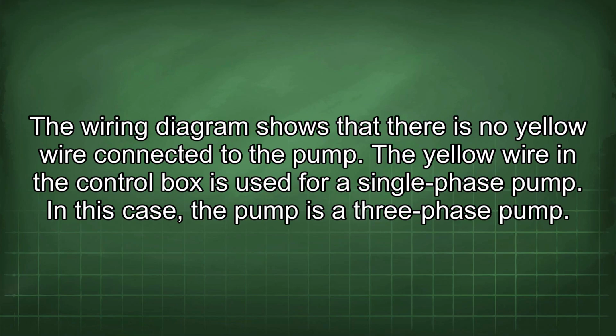The wiring diagram shows that there is no yellow wire connected to the pump. The yellow wire in the control box is used for a single-phase pump. In this case, the pump is a three-phase pump.